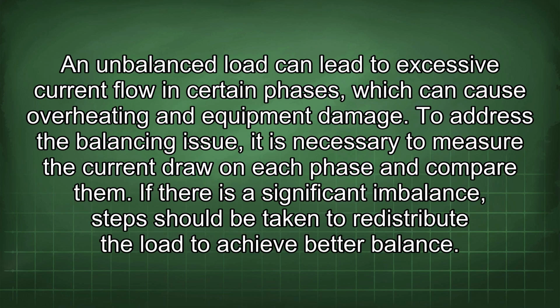An unbalanced load can lead to excessive current flow in certain phases, which can cause overheating and equipment damage. To address the balancing issue, it is necessary to measure the current draw on each phase and compare them. If there is a significant imbalance, steps should be taken to redistribute the load to achieve better balance.